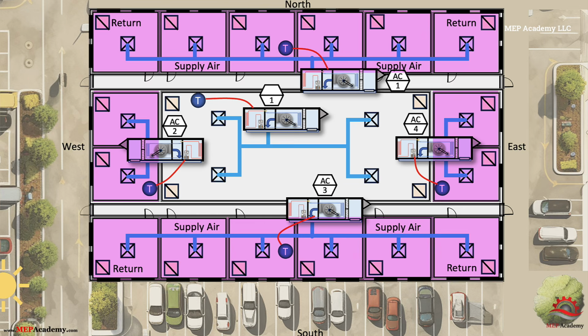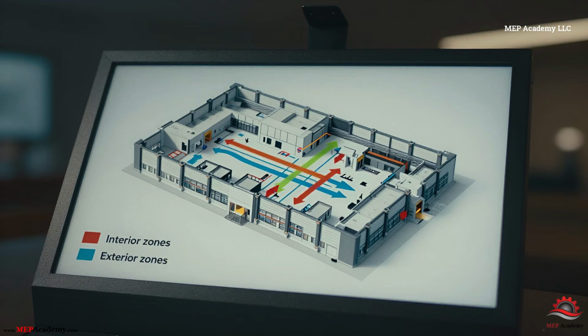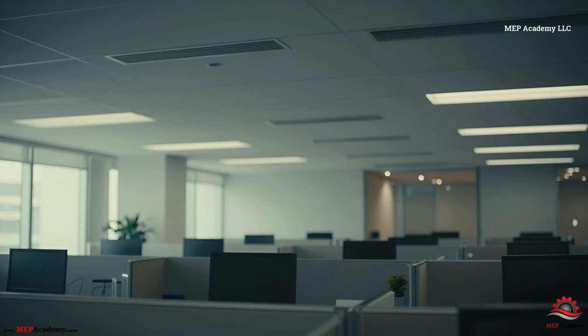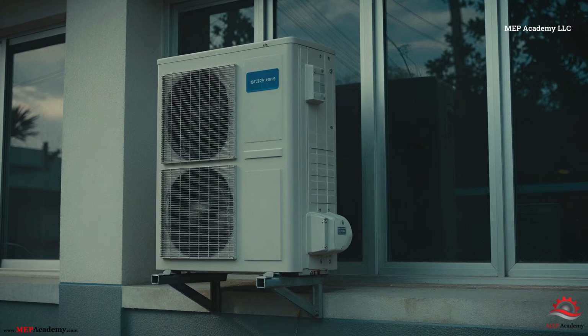Now let's look at perimeter zones which have exterior walls and windows and possibly a roof directly above. These zones experience heat loss in winter, solar gain in summer, and a constant load swing. The best choice for exterior zones might be a heat pump, as you get heating and cooling in one system. It can handle seasonal changes and eliminates separate heating equipment. Real-world design strategy. In real projects, the best designs use a hybrid approach. Interior zones use cooling-only systems, and exterior zones can use heat pumps or systems with heating capabilities.